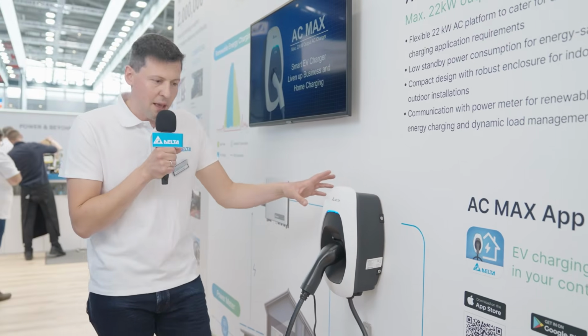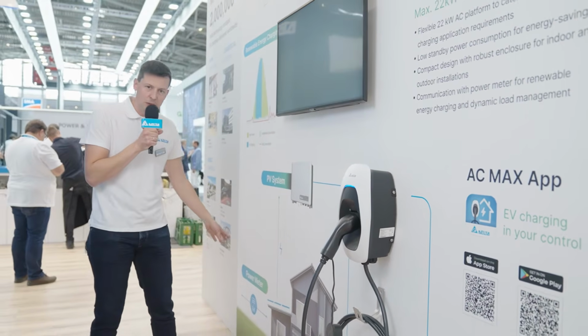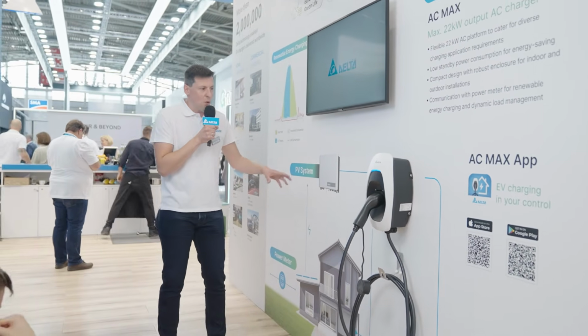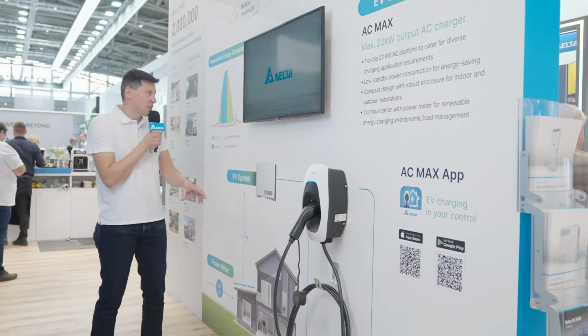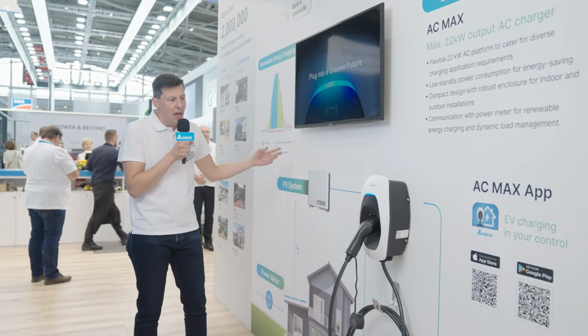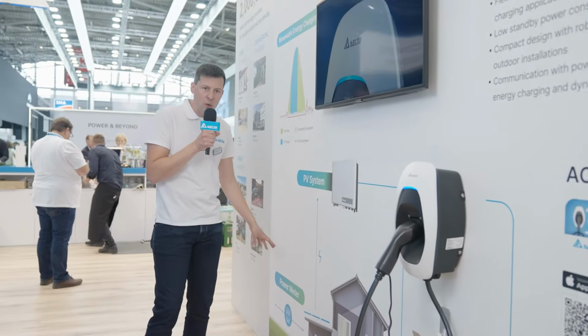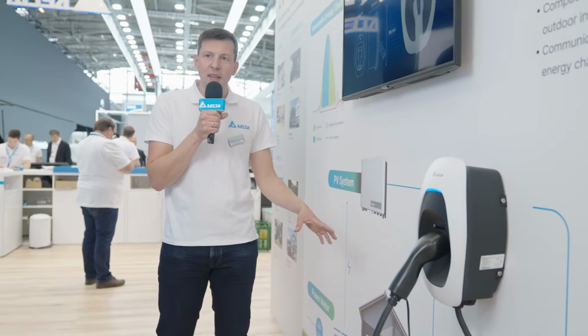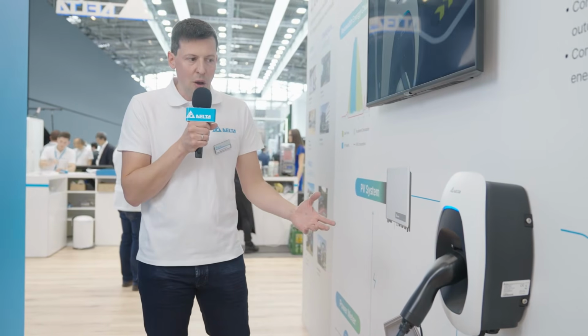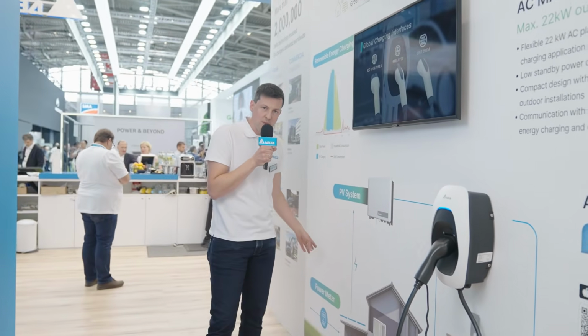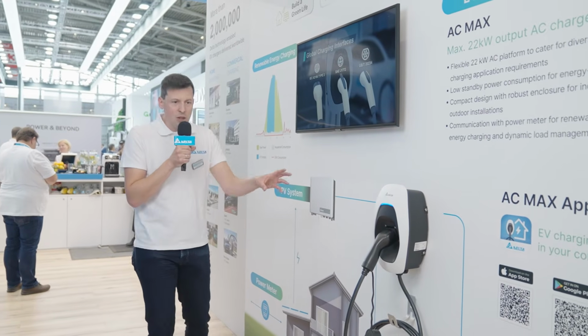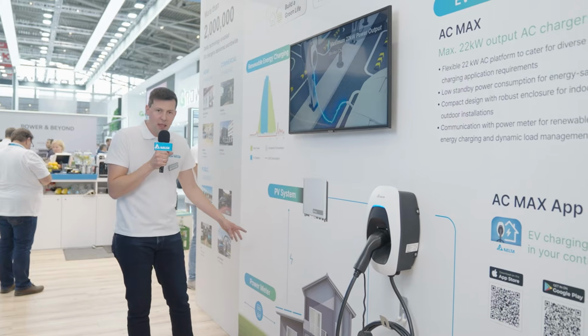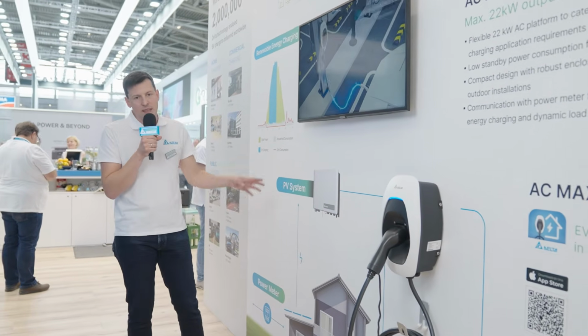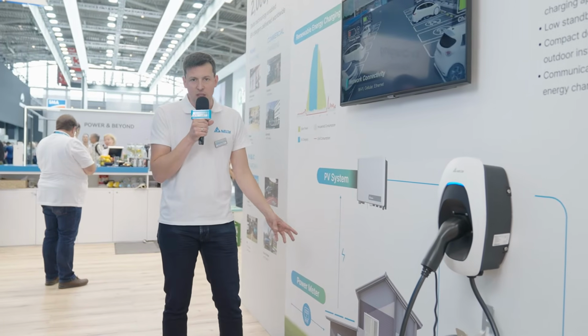We use the same setup, AC Max connected to the energy meter at the grid connection point. But this time the target isn't to optimize PV charging according to energy produced from the PV inverter - it's a control that ensures the grid connection point doesn't get overloaded. If you have appliances at the household consuming higher power while also charging your car in parallel, the grid connection point could get overloaded. With this new feature, AC Max controls all the time that the maximum power is not exceeded, adjusting the EV charging power accordingly.